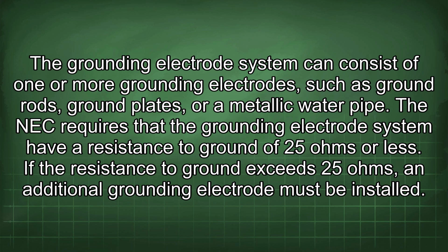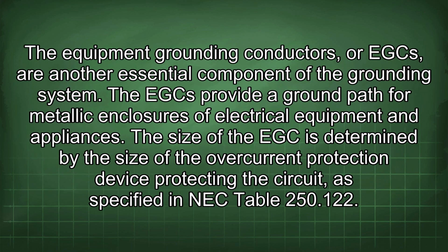a metallic water pipe. The NEC requires that the grounding electrode system have a resistance to ground of 25 ohms or less. If the resistance to ground exceeds 25 ohms, an additional grounding electrode must be installed. The equipment grounding conductors, or EGCs, are another essential component of the grounding system. The EGCs provide a ground path for metallic enclosures of electrical equipment and appliances.